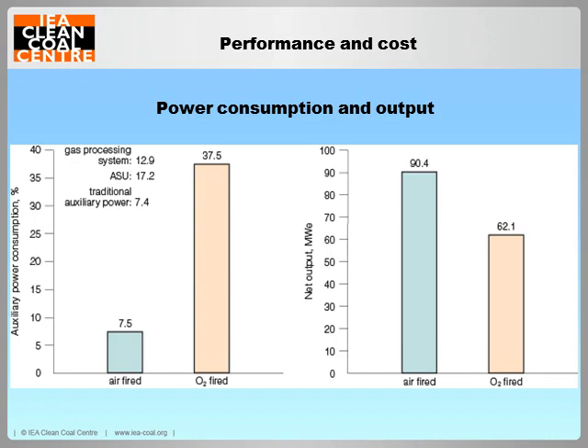The power output of the Oxy-CFB unit will be lower compared with the corresponding air-firing CFB unit due to the additional power consumption by the air separation and the CO2 processing units. In general, the efficiency penalty is about 10 percentage points in Oxy-CFB operation compared to air-firing. In terms of operation, bed agglomeration is not a major issue for a properly designed Oxy-CFB boiler. No significant changes seem to occur in emission levels of SO2 or NOx, and the emissions of other pollutants are comparable to those with air firing. The total plant cost of the Oxy-CFB plant is higher due to the relatively costly and power-consuming air separation and flue gas treatment system.